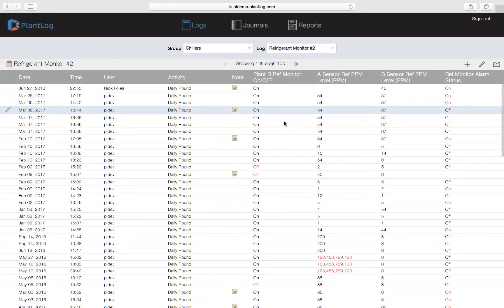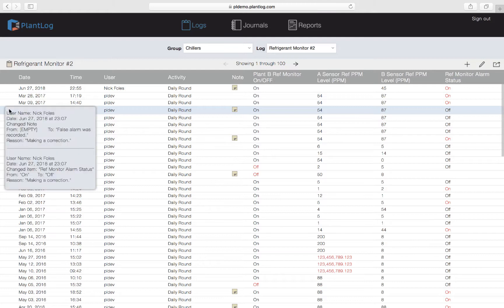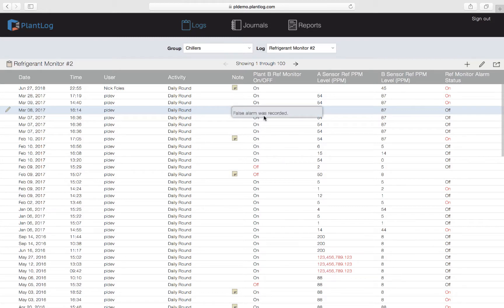The record has now been edited from its original creation point. On the far left you'll notice a yellow pencil icon — anytime you see this icon it indicates that the log record was edited from its original creation point. Hover over the pencil and a box will appear showing who made the edit, when they made it, what was changed, what the original value was, and the reason for the edit. This is the audit trail. As you can see in the updated record, there's now a note icon that wasn't there before, and the alarm status now shows Off rather than On — so it is no longer an exception.